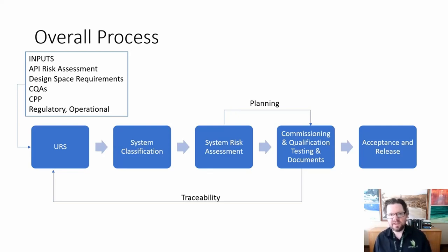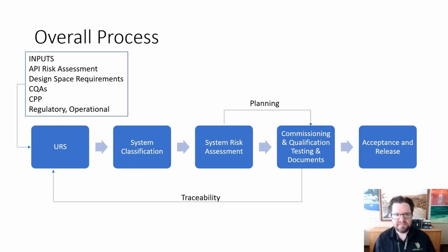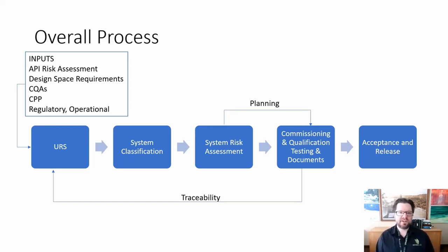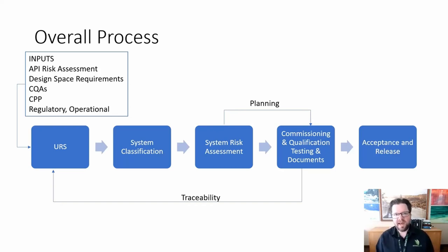Then you typically go through a system classification process — where does the equipment fit in with your systems in your design space? There's a whole process associated with that. You really need to understand whether your system and your equipment have a critical impact — is it a direct impact or no impact? You need to define that and define all the parameters and how that's going to relate to your facility.